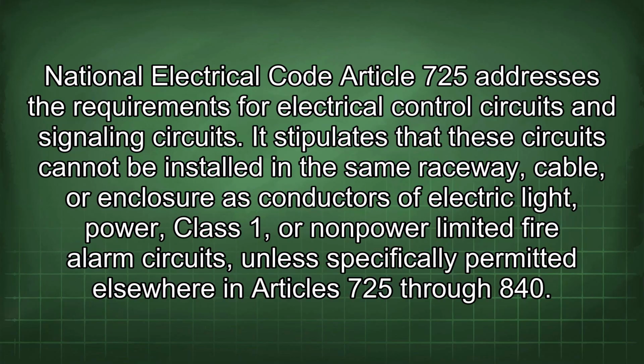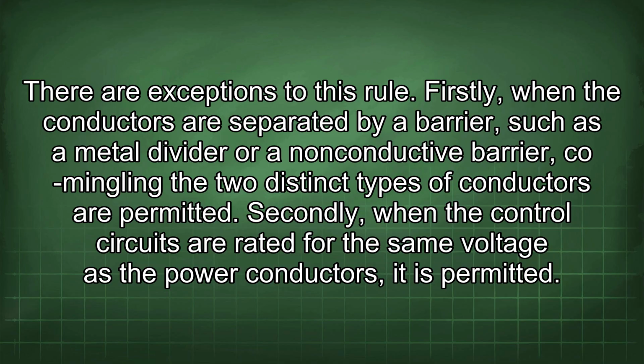National Electrical Code Article 725 addresses the requirements for electrical control circuits and signaling circuits. It stipulates that these circuits cannot be installed in the same raceway, cable, or enclosure as conductors of electric light, power, Class 1, or non-power limited fire alarm circuits, unless specifically permitted elsewhere in Articles 725 through 840. There are exceptions to this rule.